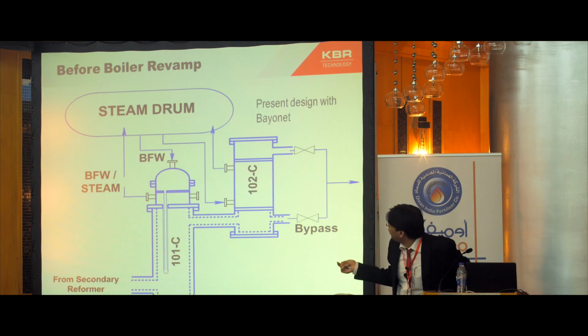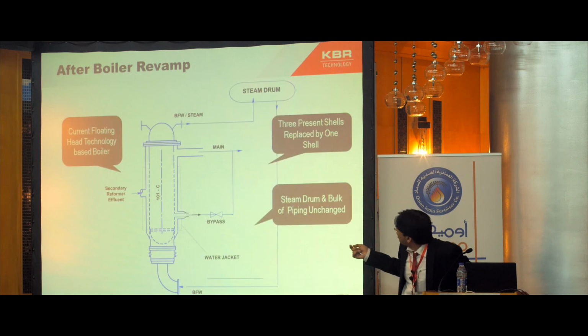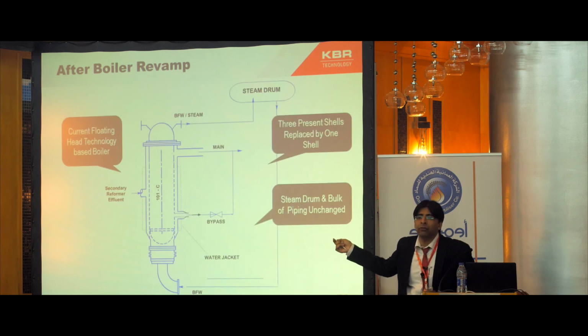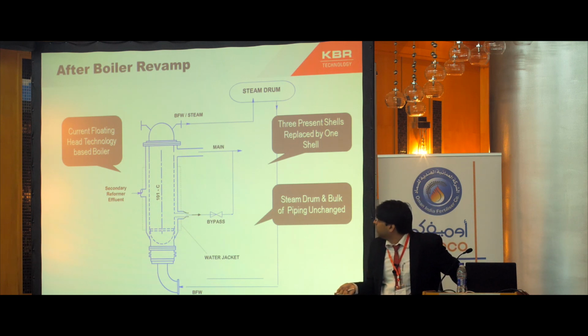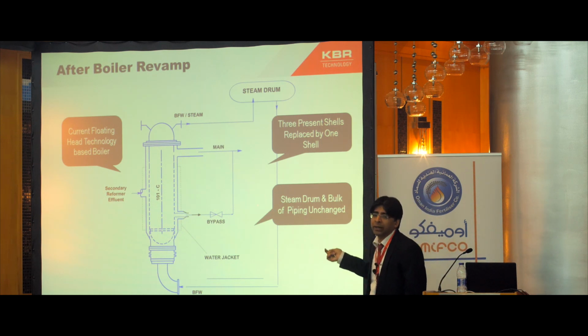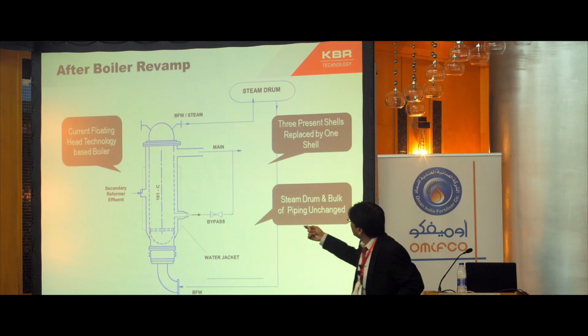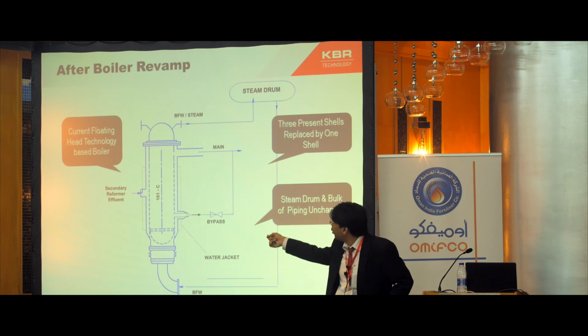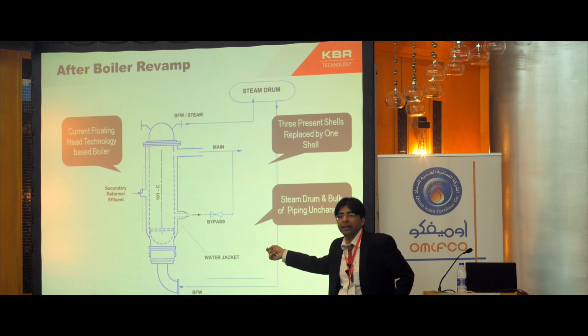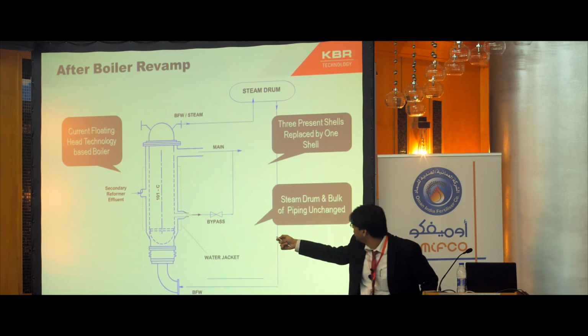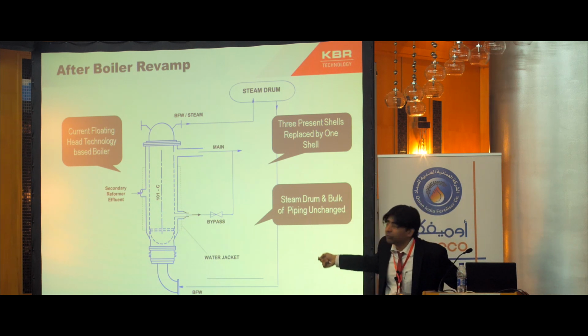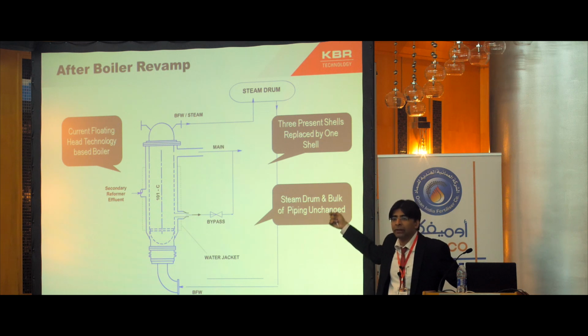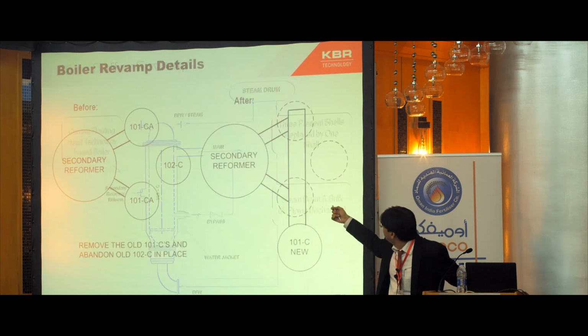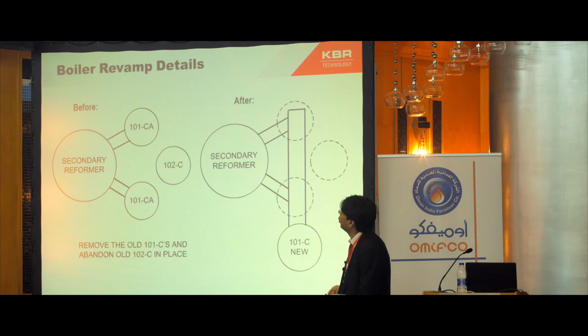Before the boiler revamp, having 3 shells, it looks like this. After the revamp, all the 3 shells will be removed and replaced with a single floating head. These will have external bypasses to control the temperature, so there is no effect on the process. The process remains the same, only the 3 shells have been replaced by a single shell. The steam drum and the bulk of the piping remain the same at the same location.